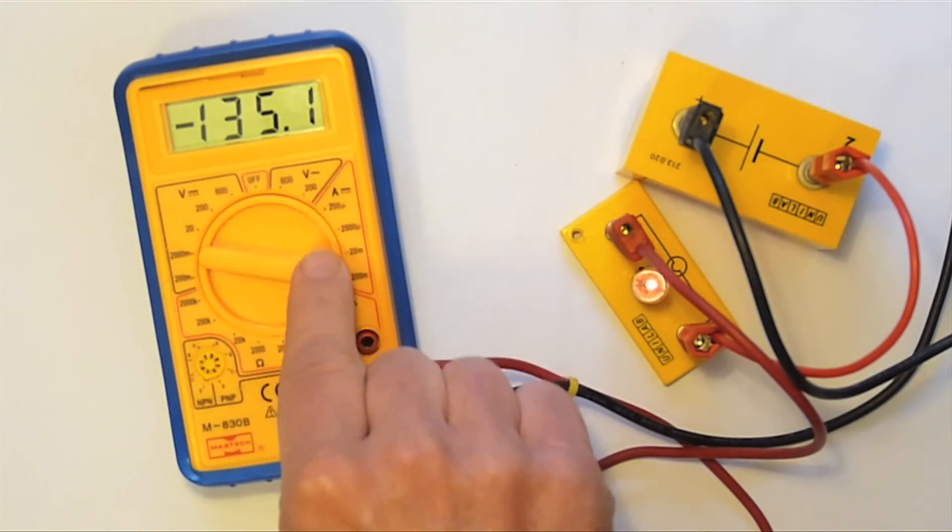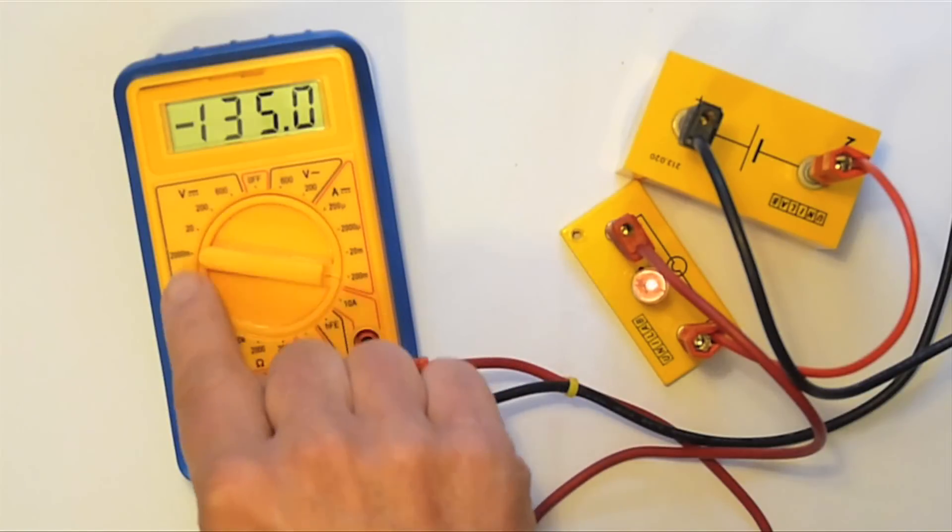If the milliamp ranges do not work at all, I just get a zero, then someone has blown the fuse. It needs to be replaced. However, the meter will still work as a voltmeter.